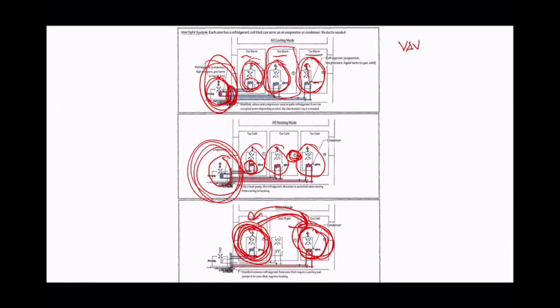In a VAV system, the advantage is—and this is a difficult topic, if you're an Amber Book user you can go through the section on HVAC—but from a VAV point of view, the advantages are that we can bring fresh air even to rooms that are in the interior, and if we have a corridor, it's not that hard to run a single duct down the corridor.